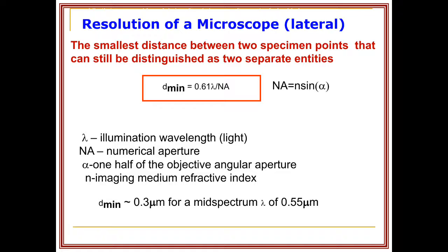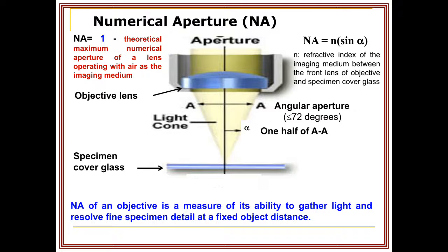Alpha (α) is one half of the objective angular aperture, and N is the imaging medium refractive index. The theoretical maximum numerical aperture value is one when operating with air as the imaging medium. N is the refractive index of the imaging medium between the front lens of the objective and the specimen and cover glass.